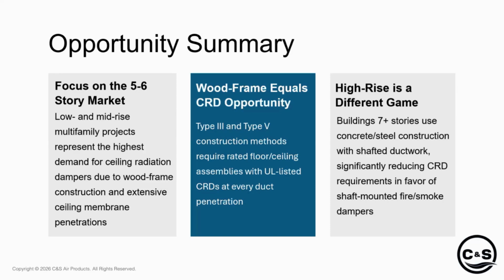So most ceiling radiation damper manufacturers said, you know what, we're just going to stick with the static designs. They seem to be the way that everyone is going about these 5 to 6 story wood constructed buildings anyway, so we'll stick with that. I think it was maybe 2 or 3 years ago, the IBC changed some language and presented the requirement for dynamic ceiling radiation dampers. It states that a dynamic ceiling radiation damper is required at the unit itself, or you have to put a firestat so the unit shuts down in the case of a fire.